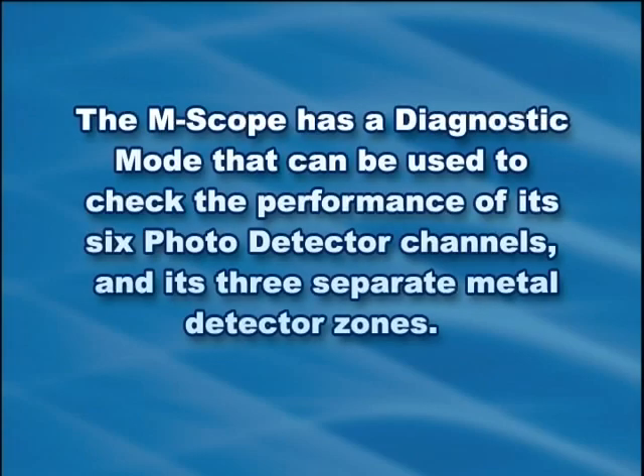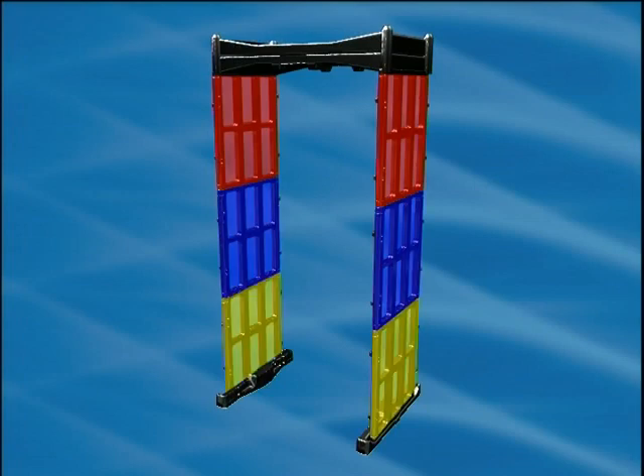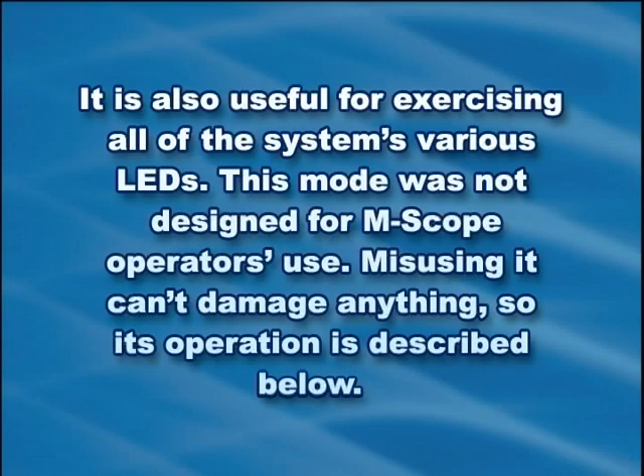The M-Scope has a diagnostic mode that can be used to check the performance of its six photo detector channels and its three separate metal detector zones. It is also useful for exercising all of the system's various LEDs. This mode was not designed for M-Scope operators' use. Misusing it can't damage anything, so its operation is described below.